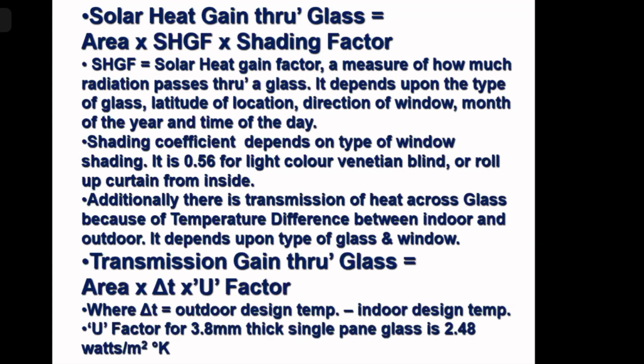U factor for 3.8 millimeter thick glass, single pane glass is 2.48. Nowadays, for large commercial building, we are using very special glasses, which are reflective glasses. Reflective glasses also, people are objecting nowadays because it reflects most of the heat, but it creates glare. So your outside environment becomes glary, and heat reflected from your building may fall on the adjacent building. So people are objecting to reflective glasses, but there are other glasses which pass only very minimum amount of heat. So very special glasses are there. So if we use them, we must consult glass manufacturer's catalog and take the U value from there. But normal clear 3.8 millimeter single pane glass is 2.48.